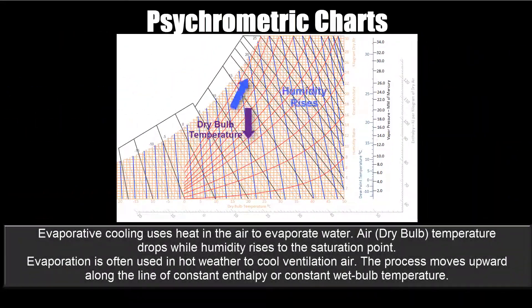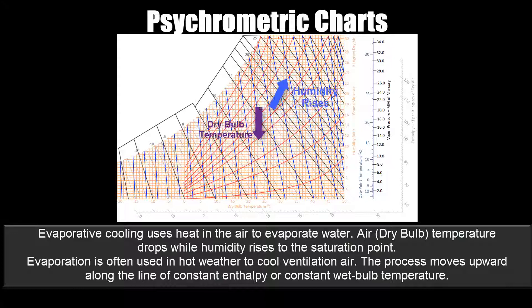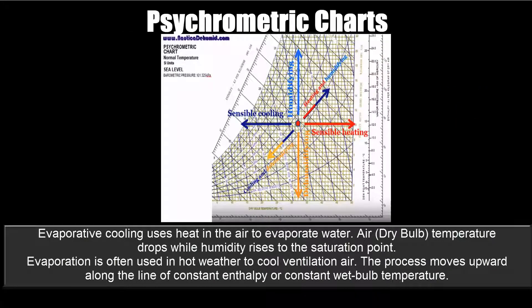Evaporative cooling uses heat in the air to evaporate water. Dry bulb temperature drops, while humidity rises to the saturation point. Evaporation is often used in hot weather to cool ventilation air. The process moves upward along the line of constant enthalpy, or constant wet bulb temperature.